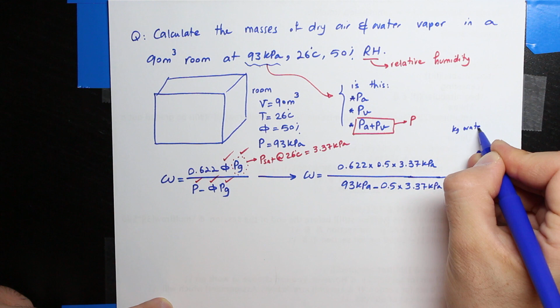If you do the math, you will end up with omega equal to 0.01147 kilogram water. Let me just write it here because the unit is very important. This has the unit of kilogram water vapor over kilogram of dry air. What does it mean? It simply means in this room, for each 1 kilogram of dry air, we have 0.01147 kilogram of water vapor within the room. It's really important to understand that this number is for each 1 kilogram of dry air.